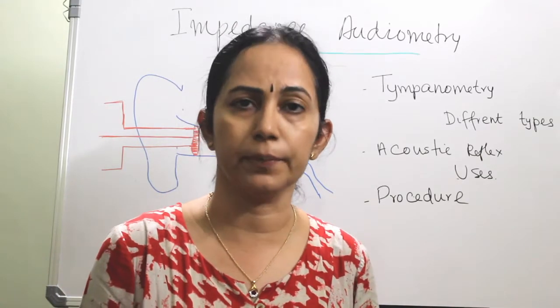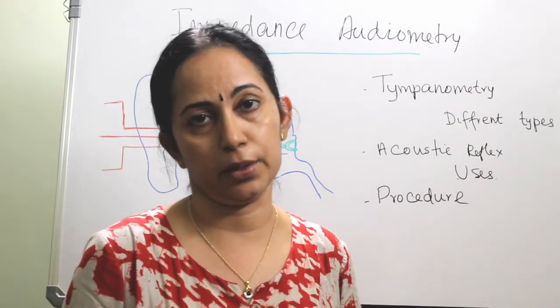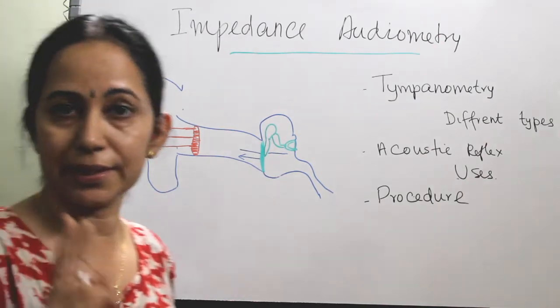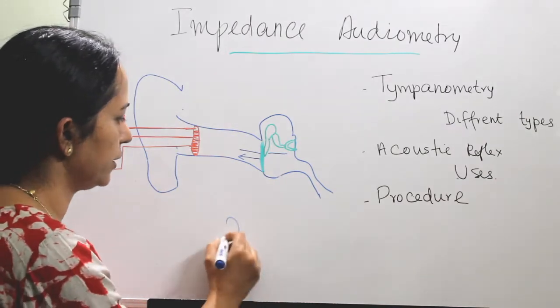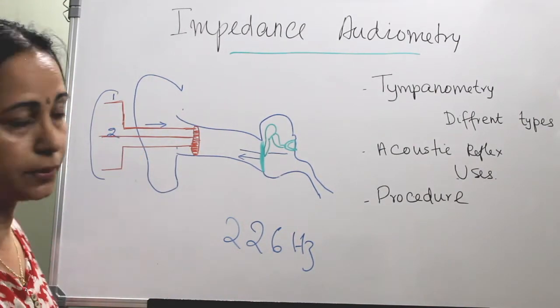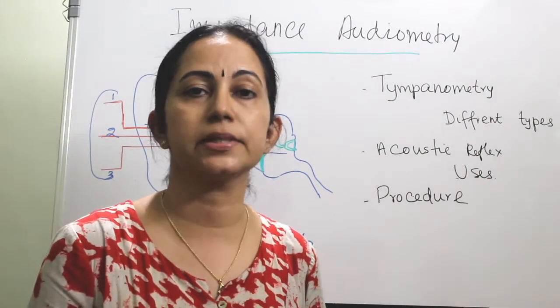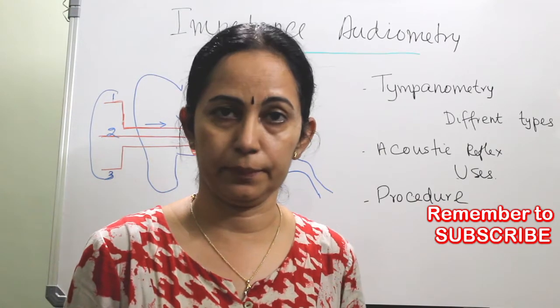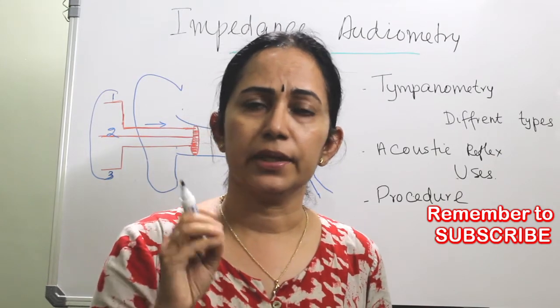In a tympanogram, we have basically a machine and a probe. The probe has got three channels: one is an oscillator which delivers the tone — for adults it is usually 226 Hz; second is an air pump which increases or decreases the pressure in the external auditory canal; and the third is a microphone which picks up and measures the amount of sound that is reflected. Since this is an objective method, very little patient cooperation is needed, so you can do this in children.